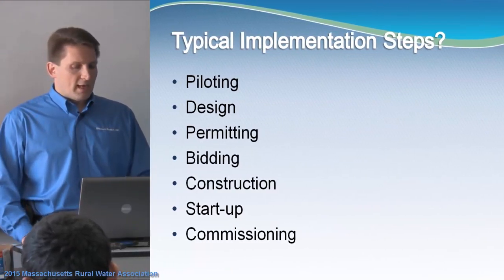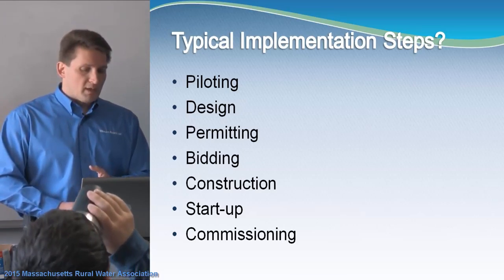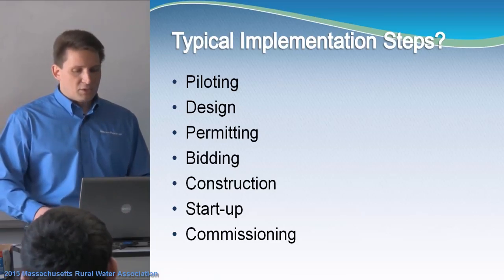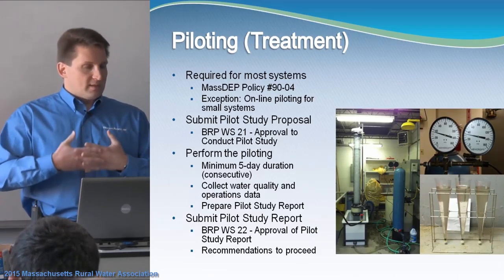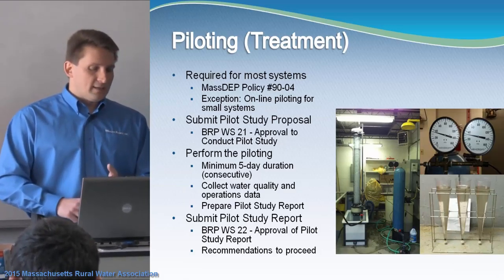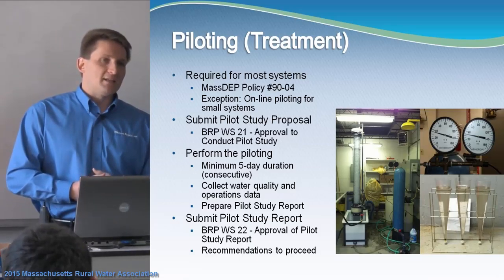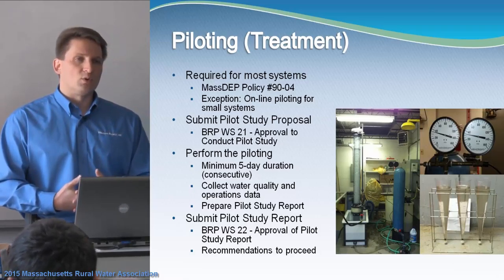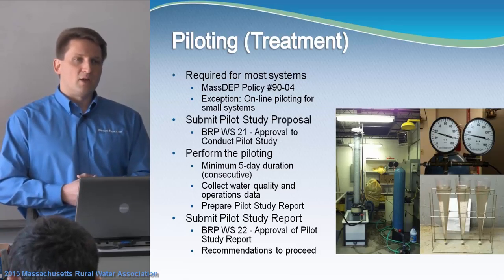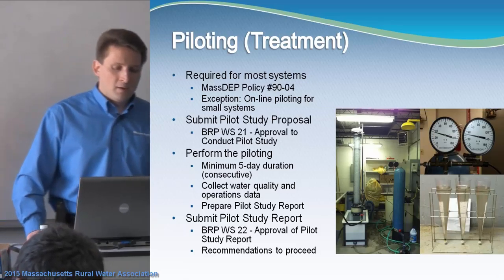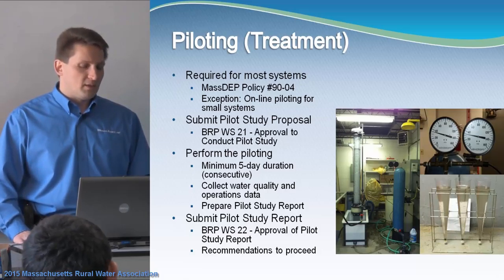Typical implementation steps for a treatment system include piloting, design, permitting, bidding and construction, startup, and commissioning. Piloting is required for most systems. MassDEP has policy 90-04, which describes what you need to do with piloting, what samples you need, and how long it needs to be. There is an exception for very small systems — like a school — where you can install a proven technology and run it through its proof-out period. We're actually going to be helping a small school in the town of Gill with that process, funded through USDA.